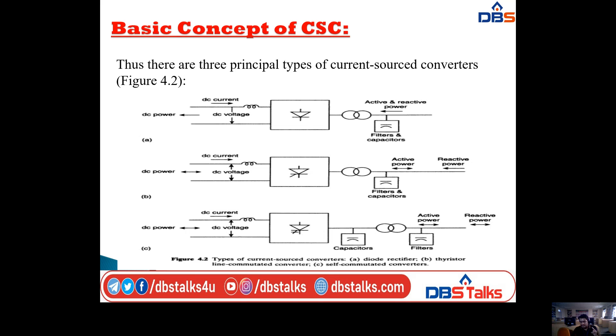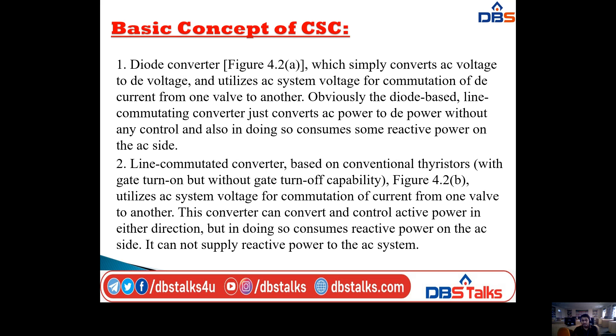In all three diagrams we have active and reactive power flows. Coming to the first type — the diode converter — which simply converts AC voltage to DC voltage and utilizes AC system voltage for commutation of DC current from one valve to another. The diode-based line-commutating converter just converts AC power to DC power without any control, and in doing so consumes some reactive power on the AC side.